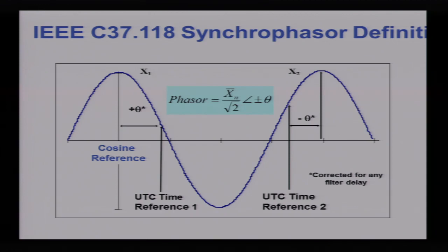That measurement point also has a peak of the fundamental waveform. The synchrophasor only looks at the fundamental frequency, not any harmonics in the waveform. In fact, the standard says that you shall reject any harmonic measurements from any synchrophasor measurement.